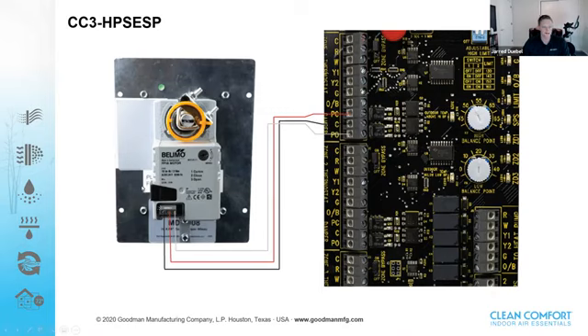This little black button, sometimes people ask, what is that? That's a clutch. If you, for some reason, lost power to the system and you needed to move that zone damper open for short term, you just push in that little clutch and you can move the zone damper. Also, if you ever have a situation where you need to switch out a motor, you just have this little shaft collar, you loosen these two, I think they're 5/16 nuts, and loosen them right up. You slide that motor right on and off. It's very simple to do. And lastly, this orange ring right here, that's a position indicator. So since this orange ring is pointing in this direction, I know that it is directly parallel with my damper, so I know that damper is in the open position.